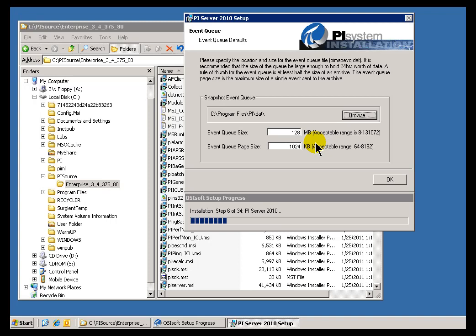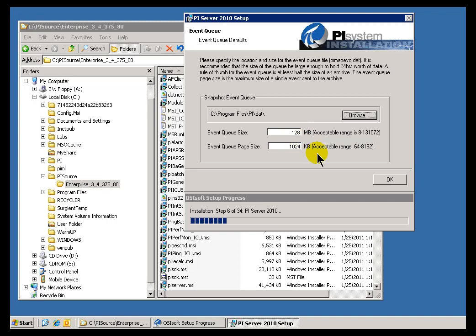Our general rule of thumb for the Event Queue Size is make it big enough to accept or be able to hold one day's worth of data. And again, you're not going to know what one day's worth of data is for you on disk until you start collecting data. So that's something that you can accept the default, and then later on through some PI System Management Tools, you can make a change to this if you need to.